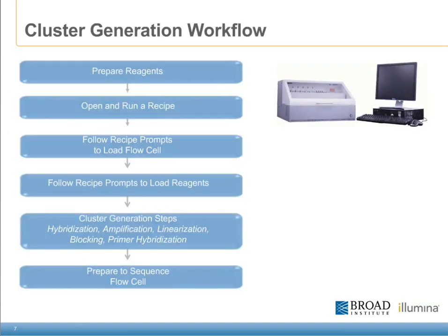The cluster generation workflow is pretty simple. It starts by preparation of the cluster reagent. You open the software to run the cluster generation recipe — slight differences for paired-end and single reads, but basically very similar. We load the recipe, put the flow cell on, and follow the recipe prompts to prime the system and load the reagents. We'll go through the cluster generation steps of template hybridization, amplification, linearization, blocking, and primer hybridization, which will prepare our flow cell for sequencing on the genome analyzer.